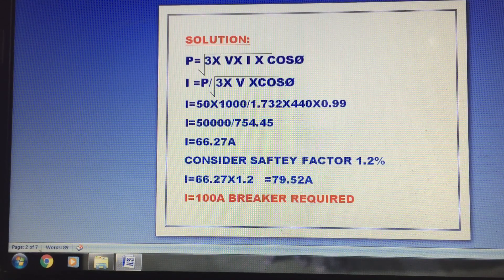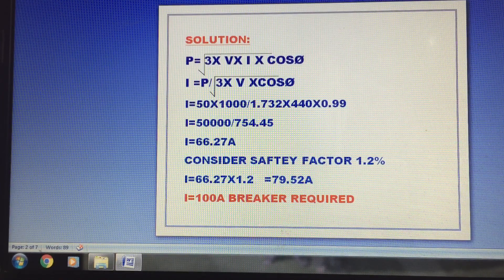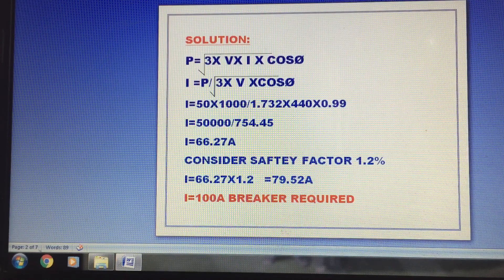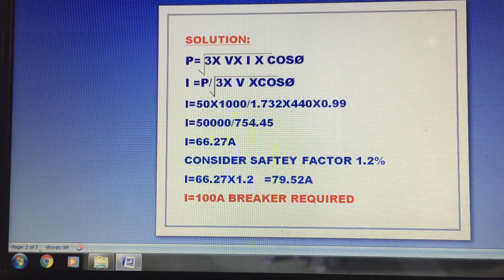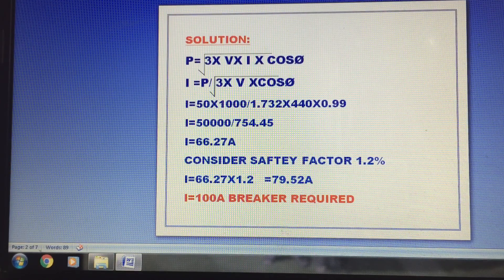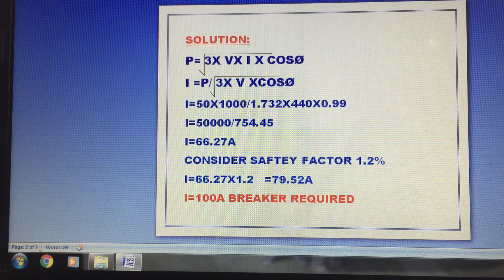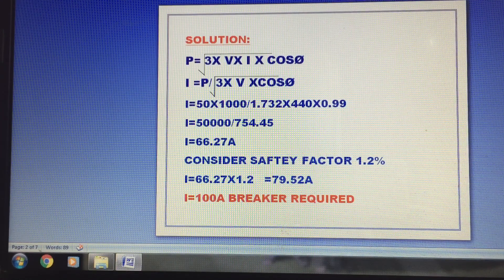Divided by root 3, which is approximately 1.732 for three phase, multiplied by 440 volt and cosφ 0.99. So I is equal to 50,000 divided by those values, giving approximately 754.45. Therefore I is equal to 66.27 amps. This is the required current. We then apply a safety factor of 125 percent, that is 1.25.